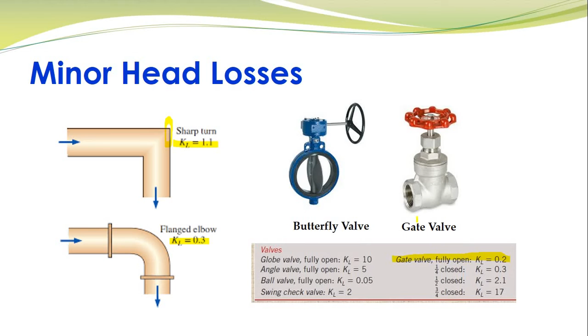Here we've got different types of valves, butterfly valve, gate valve. Valves also offer head losses in the piping network. So for instance, when you look at a gate valve, when it is fully open, the KL value is just 0.2. And when it is 3/4 closed, the KL value is 17. So there is a significant increase. When it is half closed, the KL value is 2.1. So we have to be mindful as to how we use these components in our piping network.